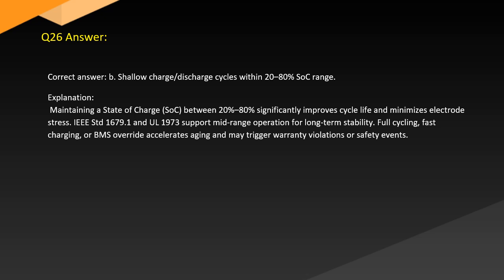Answer. Correct answer: B. Shallow charge-discharge cycles within 20-80% SOC range. Explanation. Maintaining state of charge, SOC, between 20% and 80% significantly improves cycle life and minimizes electrode stress. IEEE 1679.1 and UL 1973 support mid-range operation for long-term stability. Full cycling, fast charging, or BMS override accelerates aging and may trigger warranty violations or safety events.